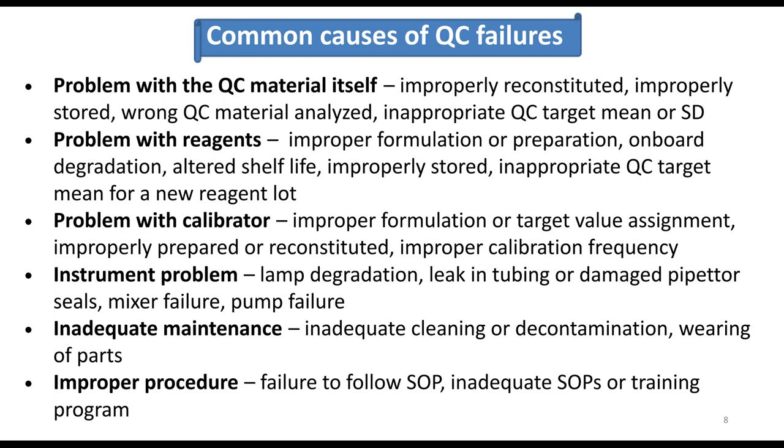So we have to remember that QC is actually a contrived material. It has additives and preservatives. It's manipulated differently than patient samples when it's being prepared by the manufacturer. And so it can have what's called a matrix effect, which means that since the QC matrix is different from that of native patient samples, the QC material can interact differently with the new reagent lot than the patient samples do.